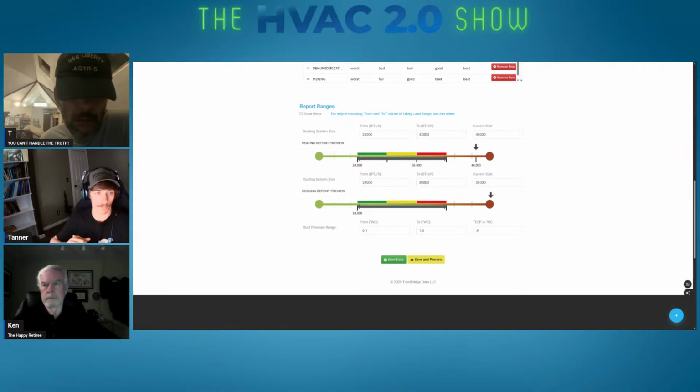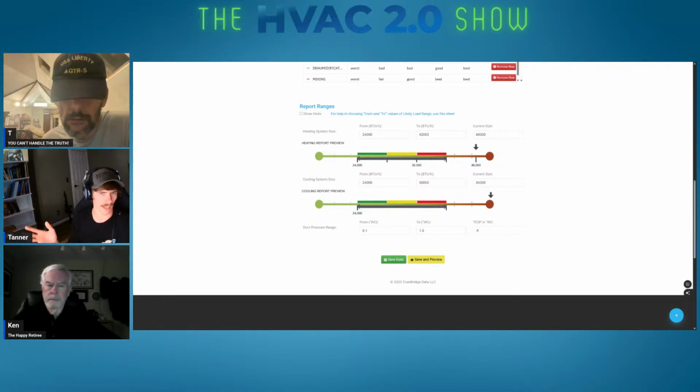So I punched it in. It's like, oh wow, you actually have a high energy EUI. You're probably losing a lot of heat up there. So we went from that to, hey, let's take a look at some things, and started crawling around. And it's like, oh, you've got Swiss cheese for ductwork. So it points you in the direction of things.